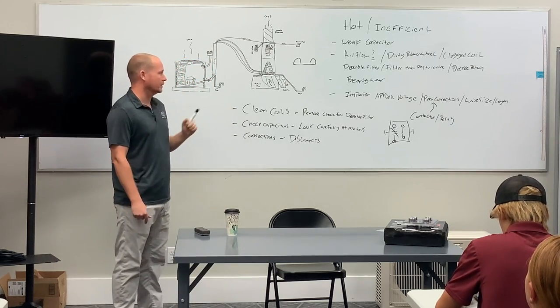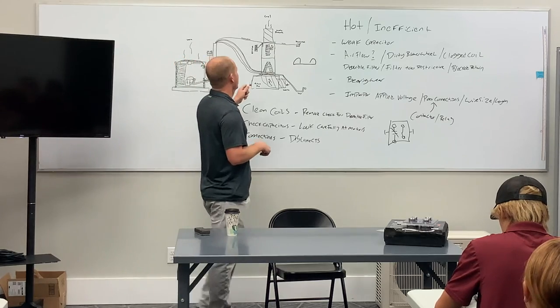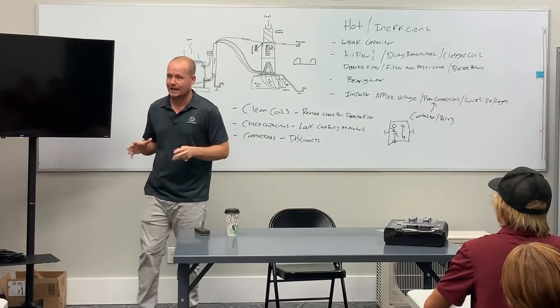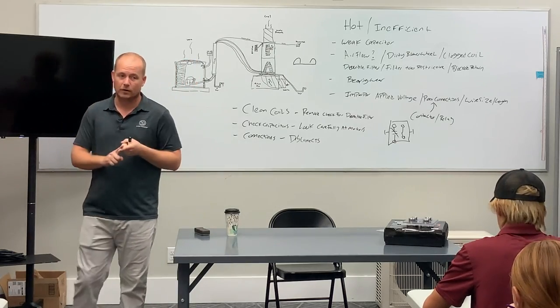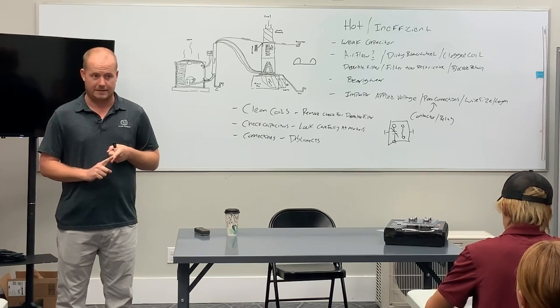Another thing that I want you to look at that we've talked a lot about, and this will be kind of the finishing thing, just a little side note, are float switches and issues related with float switches and the drains at the air handler. So horizontal portions of drains at the air handler are not insulated. That's something that should be addressed because they do sweat.